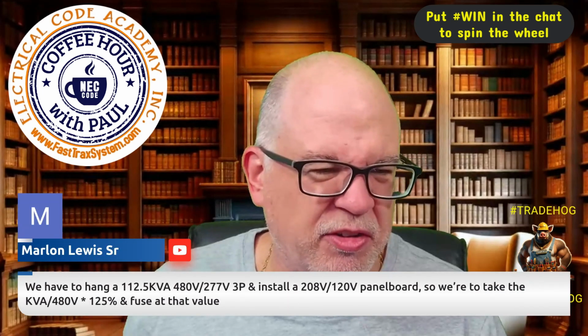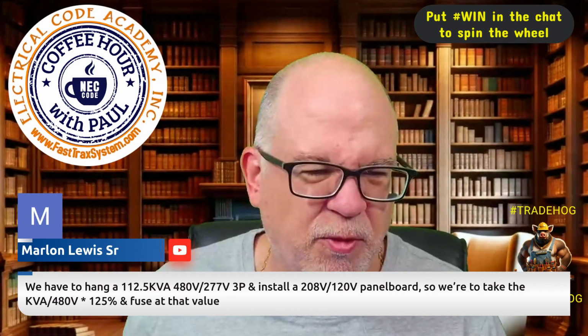So let's see. Marlon asked a question, says I have a 112.5 kVA 480-277 three-phase and install a 208 volt 120 panel board. I would say, first of all, you can't install that panel board, because if it's 277, that panel board is only rated for 208 and 120 volts. So obviously can't use that panel board. But as far as the question goes, if I'm sizing primary, let's say a 480, there's no point in having a 277 on the primary side. Why bring a neutral? It's not necessary because you're going to be deriving it from the secondary. So if you're bringing 480, ignore the 277, you're bringing 480 to the primary side, then you're going to size everything based on the kVA of the transformer, right?